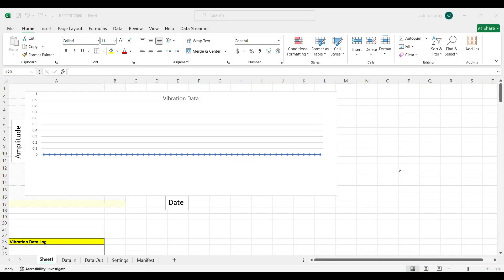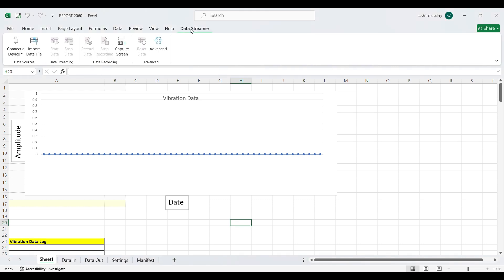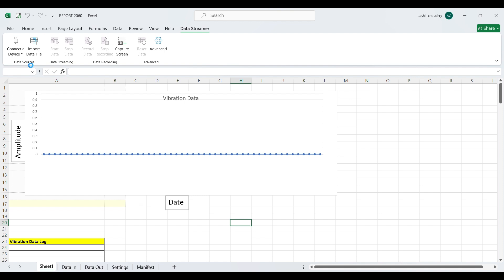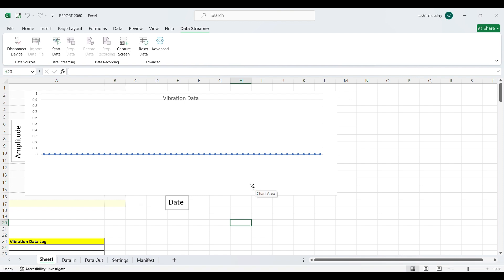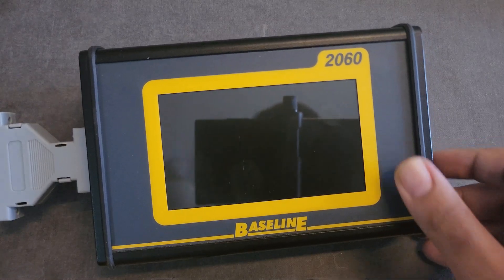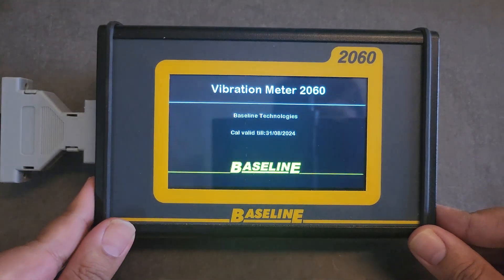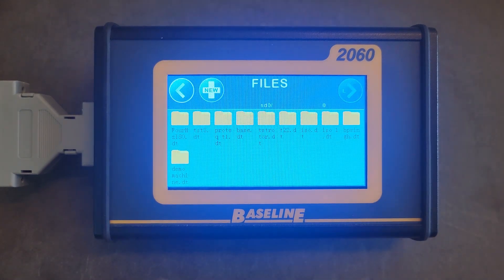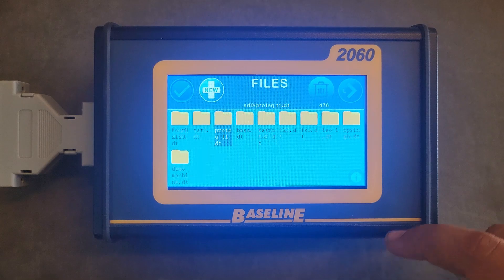Open the report format for the 2060, which is an Excel template supplied with the instrument. Go to the data streamer option and click on connect to device. Select the device recognized at COM port three. Click on start data option as shown in the video. Now the program is ready for the command to come from the instrument to stream the data. Select the machine from the file menu, press the log option, and then press the CSV button to transmit the data.